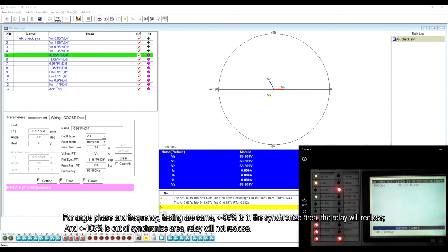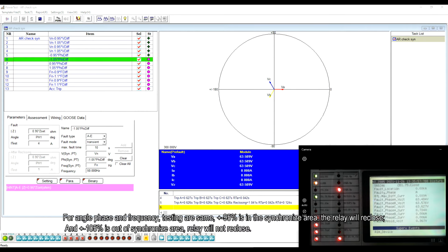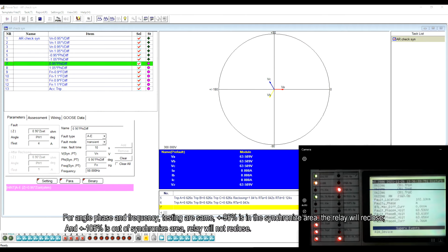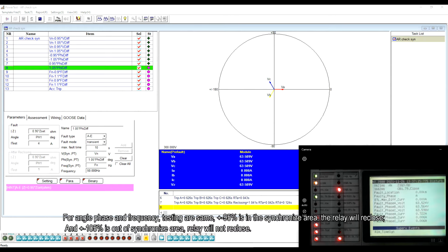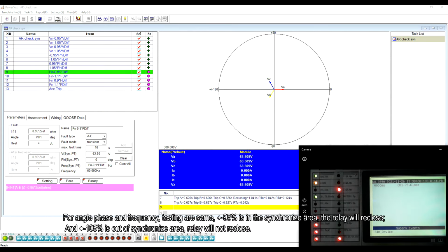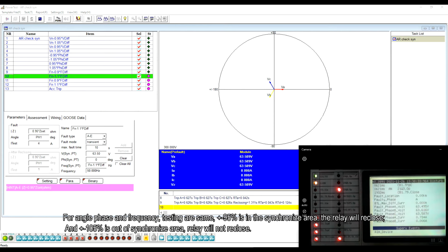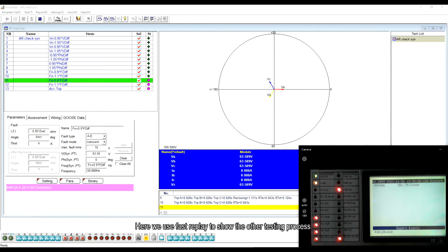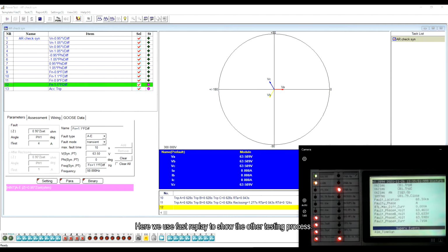For angle, phase, and the frequency testing are same. Positive and negative 95% is in the synchronized area, the relay will reclose, and positive negative 105% is out of synchronized area, and the relay will not reclose. Here we use fast replay to show the other testing process.